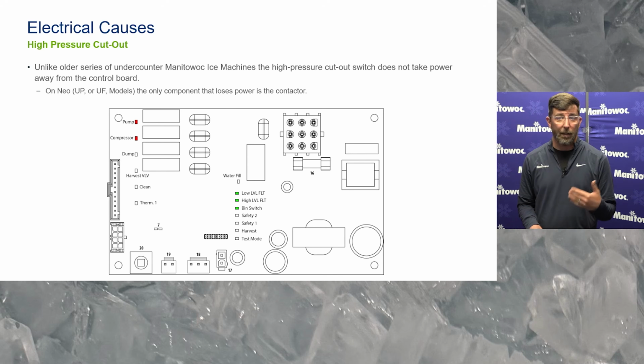And at that point, if it happens again, it's going to keep going in an infinite loop until you hit 45 minutes into freeze. 45 minutes into the freeze, guess what? The board says that's enough. We've tried. It's been 45 minutes. We have not consumed the water. We're going to initiate a harvest. We do this 3 times.